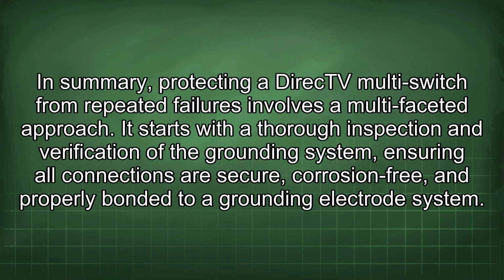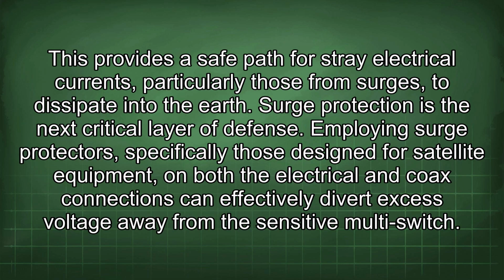It starts with a thorough inspection and verification of the grounding system, ensuring all connections are secure, corrosion-free, and properly bonded to a grounding electrode system. This provides a safe path for stray electrical currents, particularly those from surges, to dissipate into the earth.